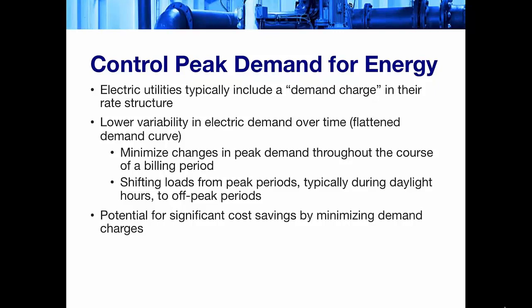and the opposite of that is if you have a lot of demand for some period of time and then very little demand later. That is typically going to be a more expensive way to operate your water distribution network and your water treatment plants, if you have a lot of spiky on-off electrical demands. So sometimes the bigger cost savings when it comes to water treatment facilities is to minimize demand charges, not necessarily reduce the total amount of energy used very much, but reduce those demand charges from your electrical utilities.